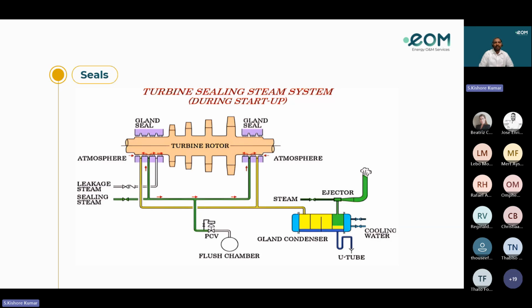Gland steam leakage will occur if the clearances of the seals are on the higher side. So maintaining proper gland seal steam pressure and temperature is essential in steam turbines. If the clearances are on the higher side, there is a possibility that the rotor may rub against the seals, the gland sealing will pass, and the steam leak will be higher, and that will lose our efficiency.